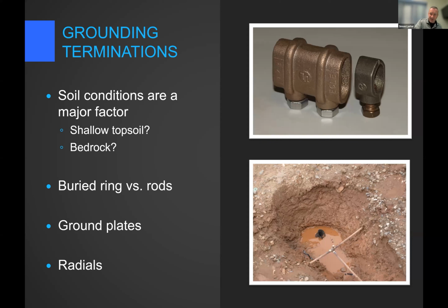Now we're getting down to the bottom here. And this, of course, you're a lot more familiar with. Soil conditions are going to be a major factor, of course, in what kind of grounding system we design. But one of the takeaways here is, once again, if you look at that picture in the upper right, you've got the acorn nut that's good for electrical grounding, and then you have the much chunkier and more substantial lightning protection ground. Once again, we have to have about 38 millimeters worth of contact, 1.5 inches of contact along the axis of that rod to make sure that's a lightning protection fitting. Much chunkier. So lightning grounding and electrical grounding are two separate animals.